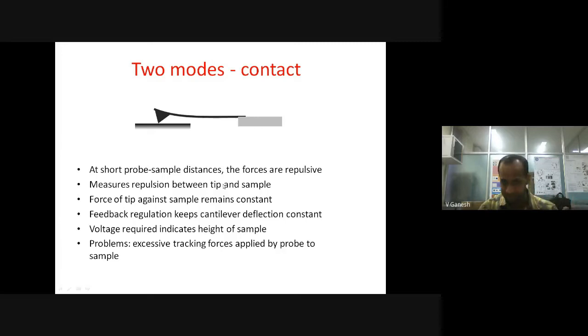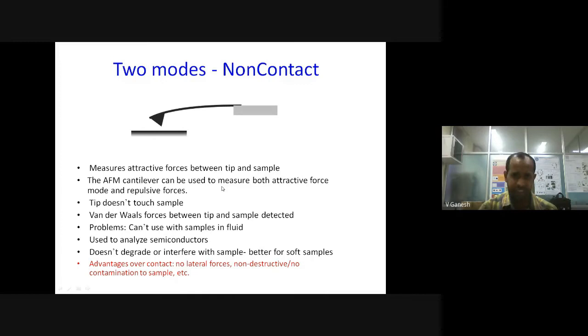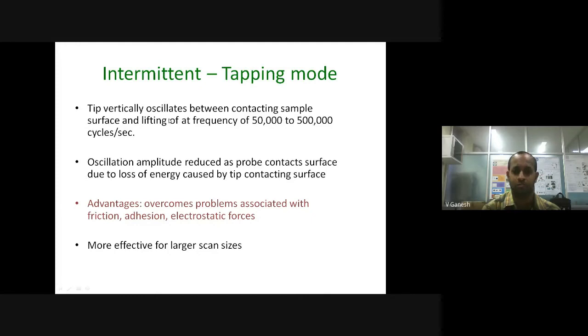Similarly, this is a kind of non-contact mode. One can also image at a slightly far away distance, but still there would be an intermolecular force of attraction or repulsion between the sample substrate and the probe. Since there would be a definite distance, the cantilever or the probe does not touch the sample substrate. So non-contact and tapping mode are the most preferred modes of operation in case of AFM.